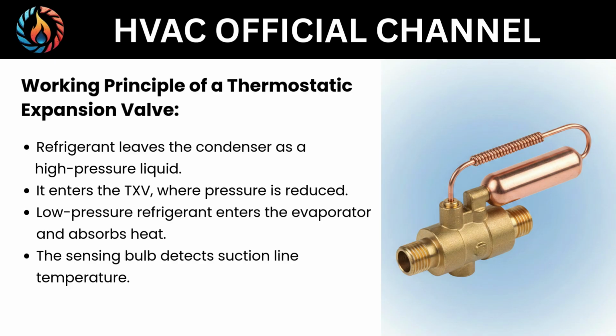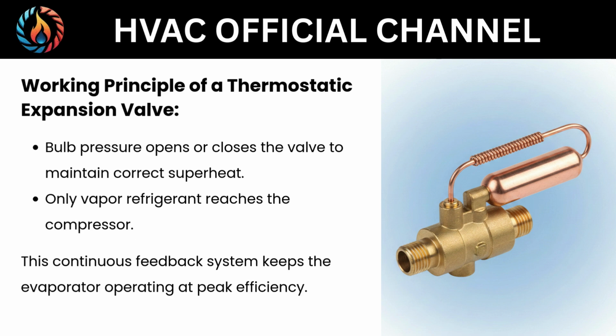Working principle of a thermostatic expansion valve. Refrigerant leaves the condenser as a high-pressure liquid. It enters the TXV, where pressure is reduced. Low-pressure refrigerant enters the evaporator and absorbs heat. The sensing bulb detects suction line temperature. Bulb pressure opens or closes the valve to maintain correct superheat. Only vapor refrigerant reaches the compressor.